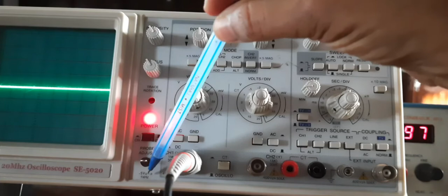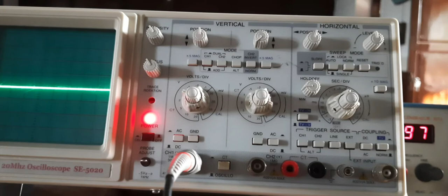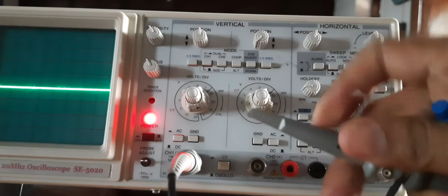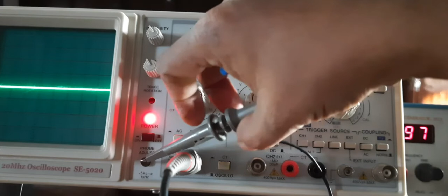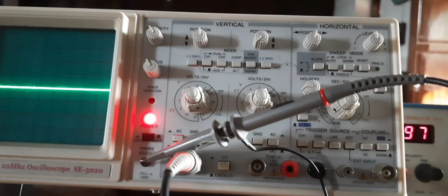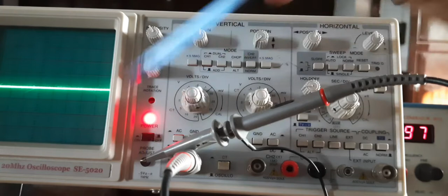So if we want to check that, what we should do is take this BNC connector for the first channel and connect it over there. So I'll disconnect it from the other source. This is my BNC connector. The positive knob, I will connect it here in this knob. The negative I need not connect because the measuring system and the source system are the same. So the negative points need not be connected. It's not compulsory. So the positive point I have connected to here.